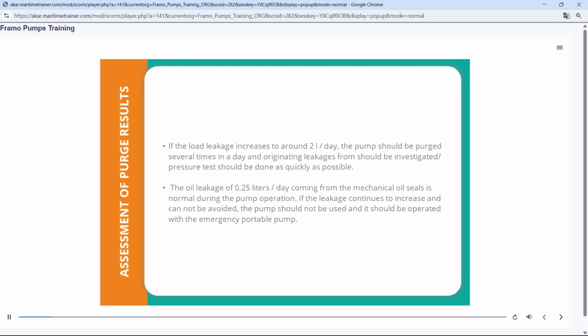If the cargo leakage increases to around 2 liters per day, the pump should be purged several times a day, and the origin of the leakage should be investigated. A pressure test should be done as quickly as possible. Oil leakage of 0.25 liters per day coming from the mechanical oil seals is normal during pump operation. If the leakage continues to increase and cannot be avoided, the pump should not be used and the cargo should be handled with the emergency portable pump.